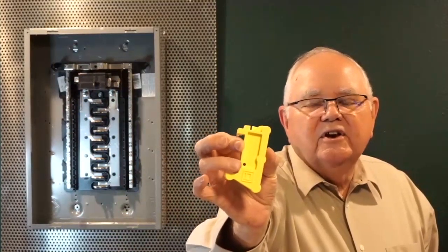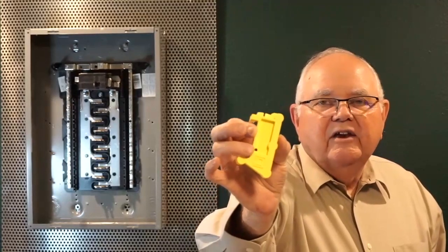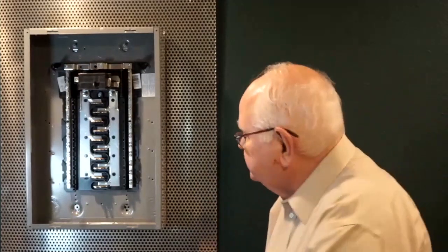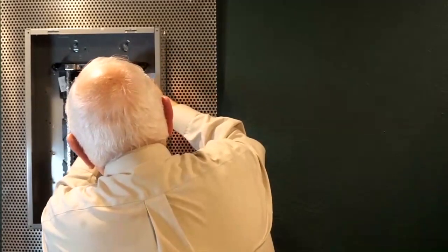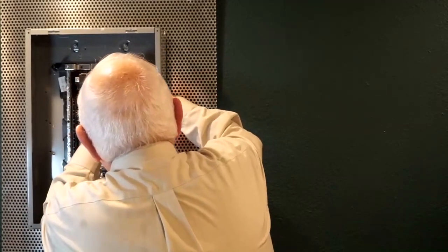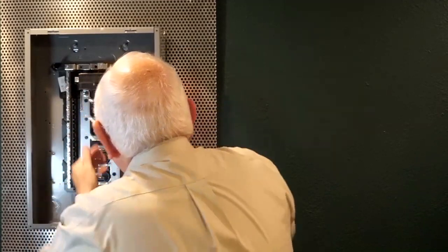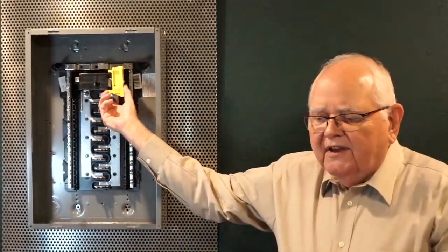And you can see down here, there's a little hole that allows you to stick your meter in order to take a reading, see whether it's energized or not. So I'll just put this in place and show you where it goes. Just snaps in place like that then. So that's if it were a service panel. Now, other things you'll obviously see out there in the field is Lexan shields, trade name for a polycarbonate material, a clear plastic shield that we often see. Keep in mind, those only protect you against inadvertently touching something and being shocked. Those shields, these barriers do not provide you any arc flash protection then.